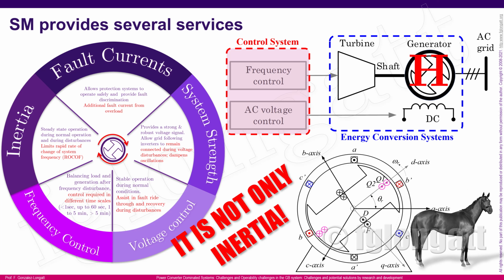For instance, a synchronous machine, if we apply a three-phase short circuit on the stator, you will get short circuit currents that can be several times the nominal current. For many years, that was very important information that we used to protect the machines using something called overcurrent protection. To be honest, that is a natural property of the synchronous machine - the machine responds with this huge current, and the machine is able to handle that kind of current.